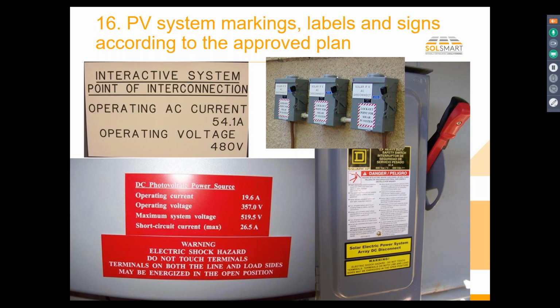That's because when we open a DC switch, we've got PV on one side. If it's daylight, that side's energized. And on the other side of the switch, we typically have an inverter like this. It's got a bunch of capacitors in it, and it could take up to 5 minutes to de-energize. And so you want to make sure that at least the electrician's given some kind of a warning, whether they read it or not. You put your screwdriver on the low side of that switch, and you didn't wait the amount of time, you didn't check to make sure that the voltage was down, you're going to get hit. So that's what that sign's about.